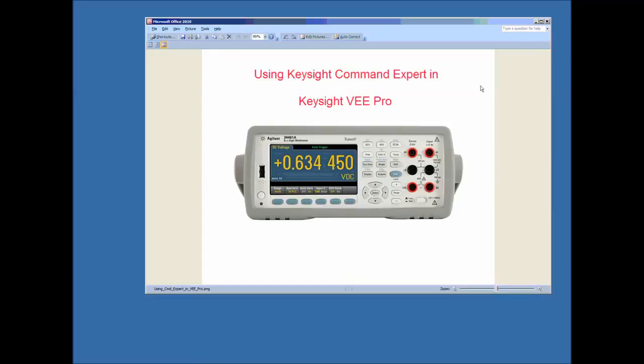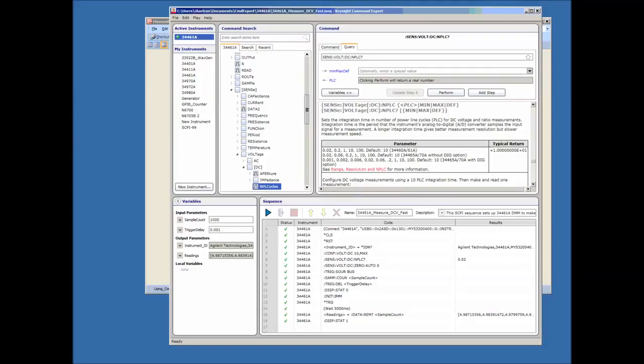The next thing I want to do is bring up Command Expert. This is the sequence that I've already created ahead of time. It basically starts the meter from a known state and then configures and optimizes it to make readings as fast as possible. One of the tools inside Command Expert is the ability to define parameters, which are helpful to use as variables inside your VEE program. I have a couple of input parameters—sample count and trigger delay—and a couple of output parameters: the instrument identification string and the actual readings we're going to capture from the meter.